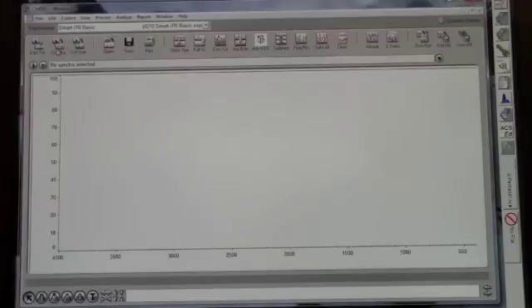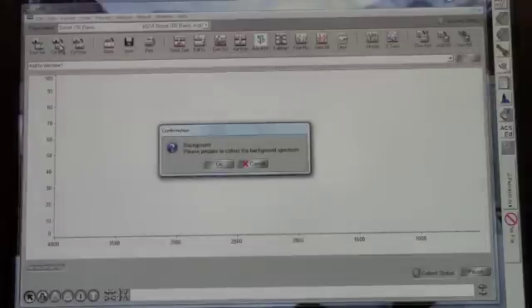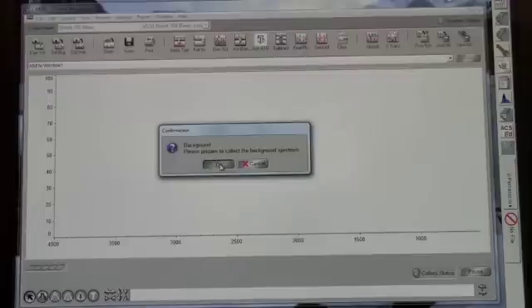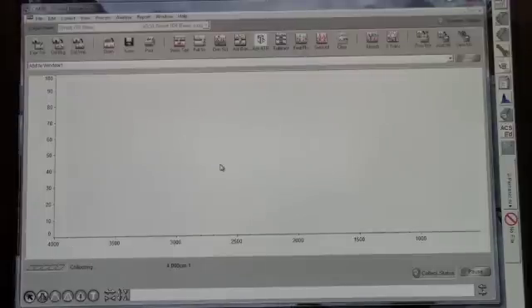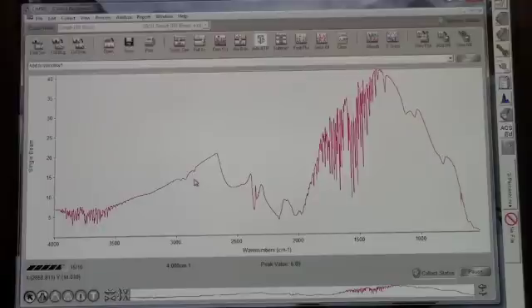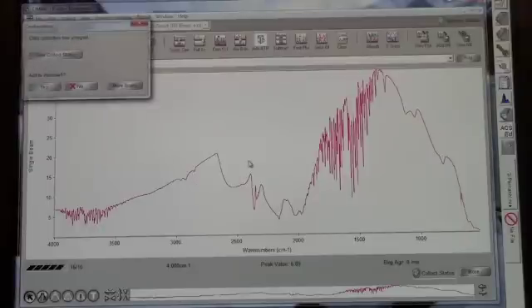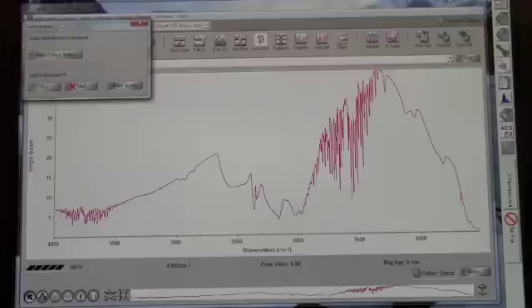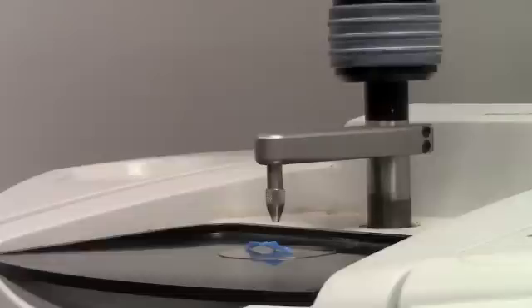The first step in testing a sample is to collect background data with no sample in place in order to calibrate the FTIR. To do this, simply click the Collect Background button in OMNIC, and then click OK. Prior to collecting the data, the number of runs can be increased to greater than the standard number of 16. This increases the accuracy of the data, but also makes the test take longer. Collecting background data usually takes around 10 to 15 seconds for 16 runs. After the data is collected, you will be prompted and you will select No for Add to Window 1.